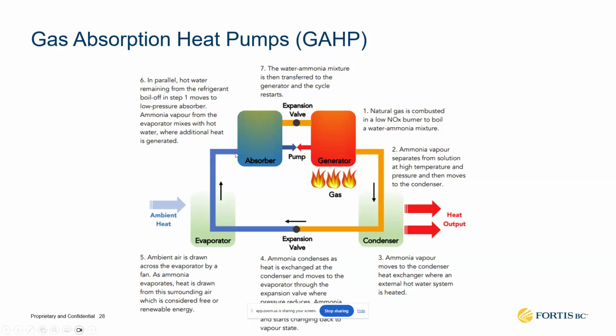When the ammonia leaves the evaporator, it's mixing in the absorber with a liquid. This liquid could be water, could be a brine, could be a proprietary liquid that absorbs the ammonia, and the liquid forms a gas liquid solution. Then this solution goes through a pump that raises the pressure of the solution, and then it goes into a gas burner. So these gas burners do two things. One is raising the temperature, and by raising the temperature of the solution, the ammonia will boil out of the mix, and then will go through the condenser for your heat rejection. The remaining liquid will go back to the absorber to continue the cycle.